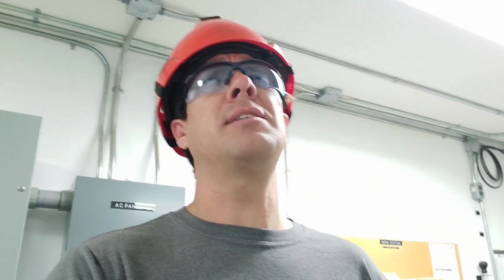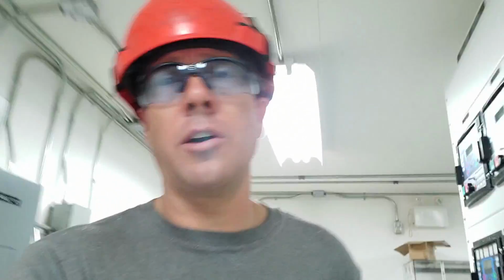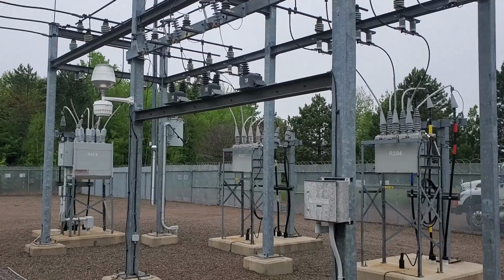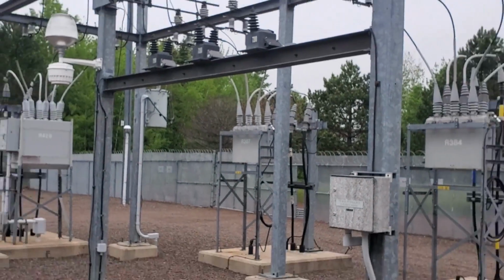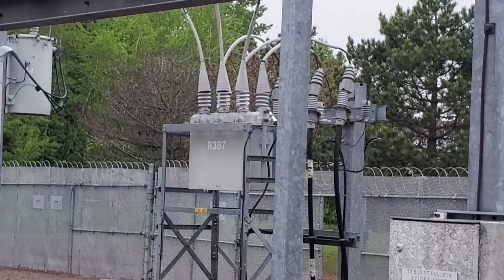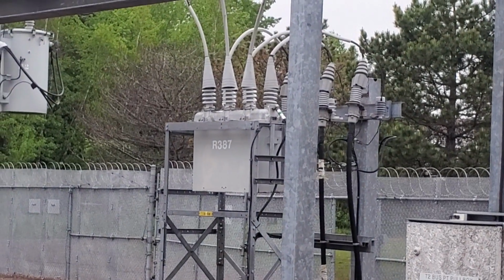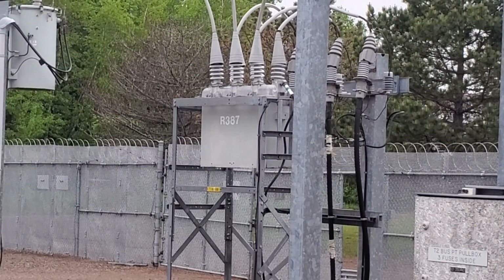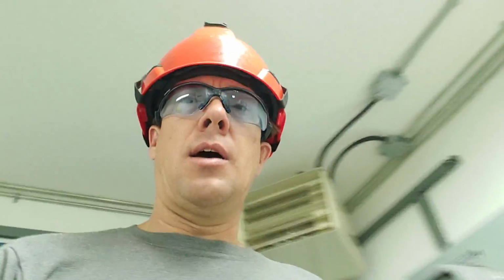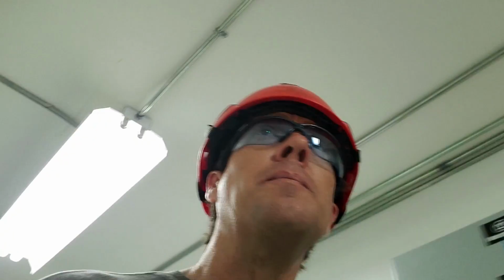That particular one is a little bit primitive. There's a counter, that's it. We can't get any more information, as it's not tied to a control panel like these guys. Outside of our sub, we've got the same oil reclosers. Let's flip this camera around. There's a couple reclosers, 3 of them in view here now. This guy here is pretty much the same equipment that was on the pole in that video. The difference is I can remotely operate that from inside the building.